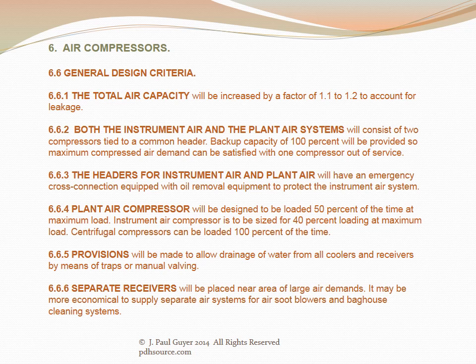Instrument air compressor is to be sized for 40 percent loading at maximum load; centrifugal compressors can be loaded 100 percent of the time. Provisions will be made to allow drainage of water from all coolers and receivers by means of traps or manual valving. Separate receivers will be placed near areas of large air demands. It may be more economical to supply separate air systems for air soot blowers and baghouse cleaning systems.